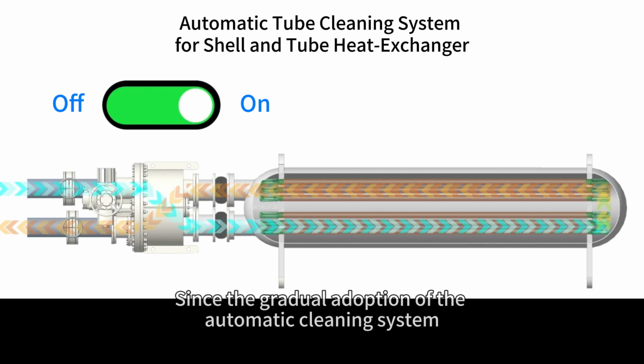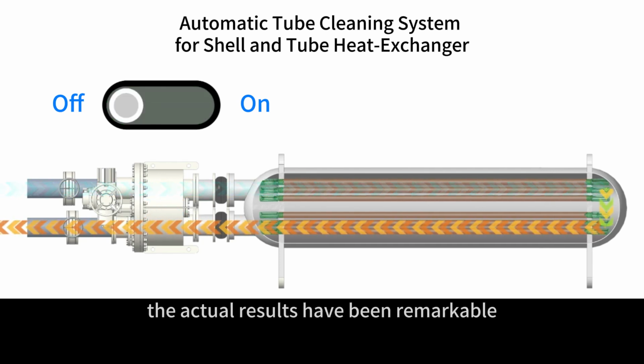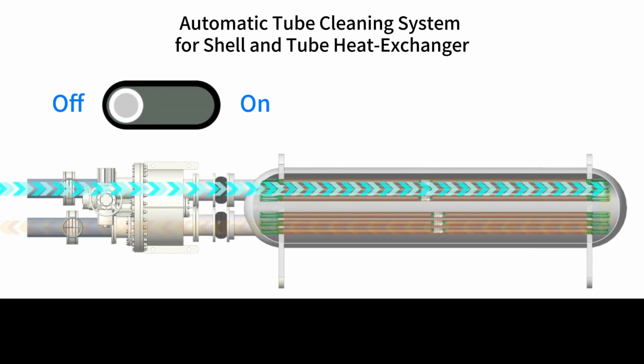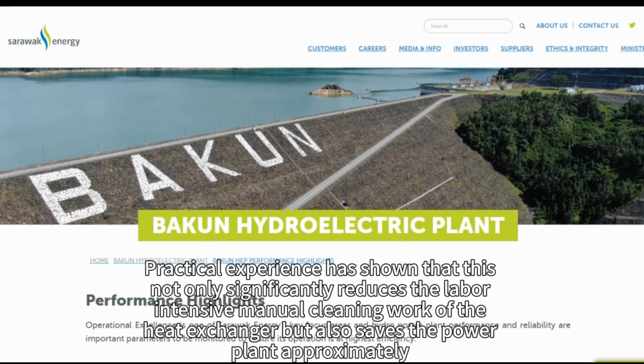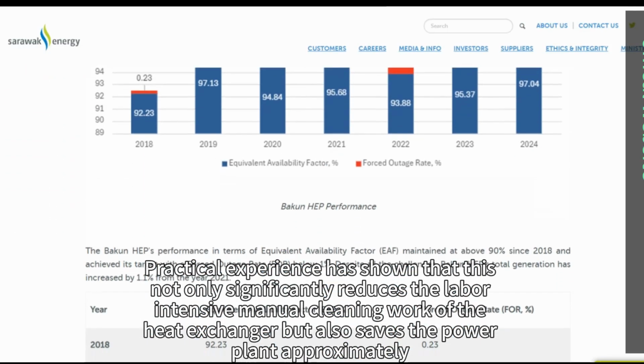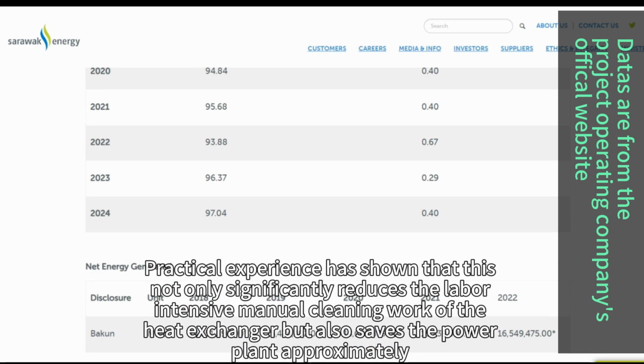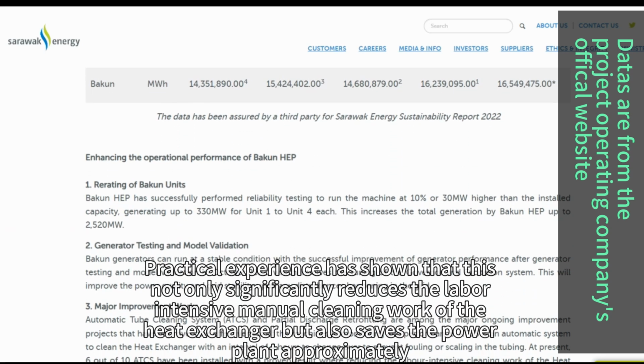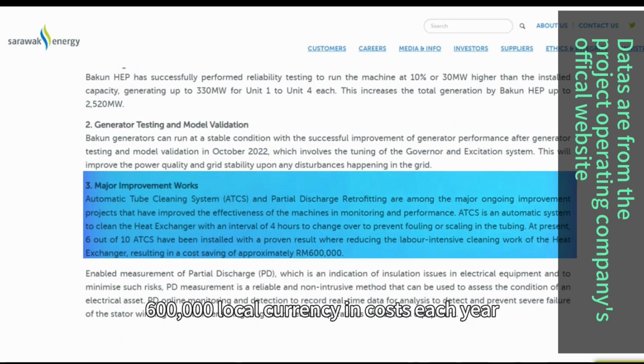Since the gradual adoption of the automatic cleaning system, the actual results have been remarkable. Currently, 6 out of 10 systems have been installed. Practical experience has shown that this not only significantly reduces the labor-intensive manual cleaning work of the heat exchanger, but also saves the power plant approximately 600,000 local currency in costs each year.